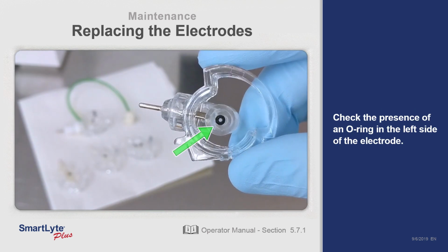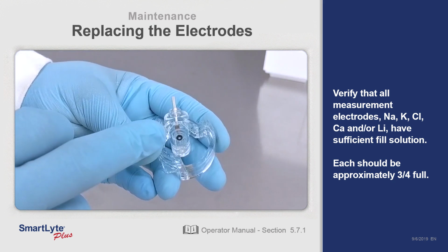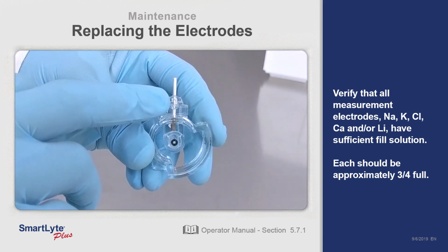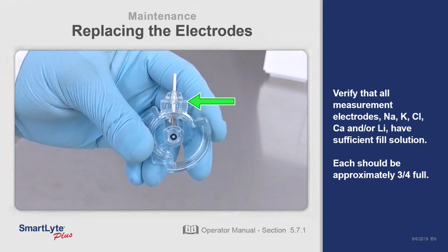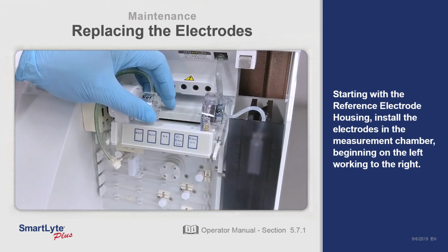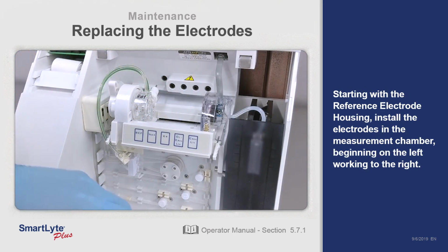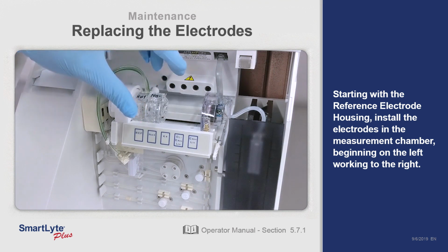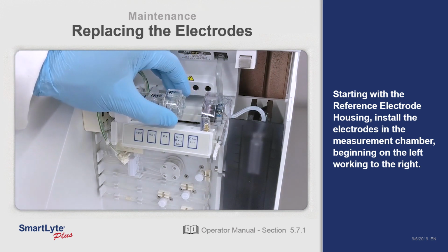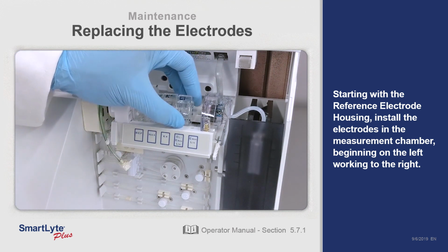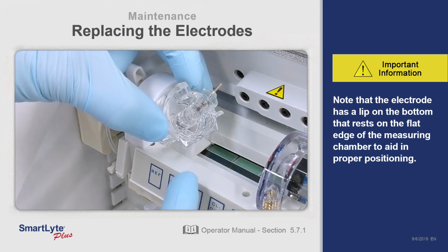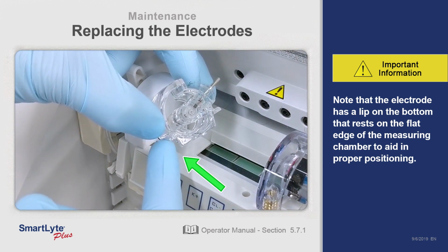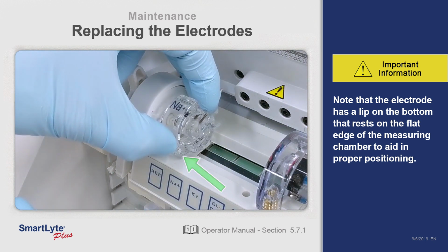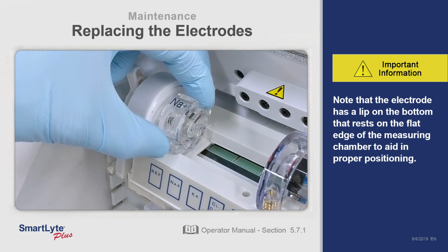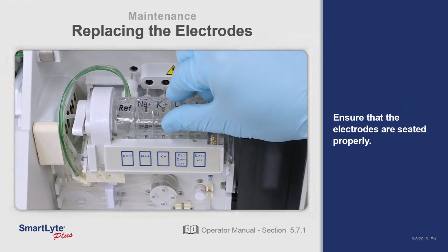Check the presence of an O-ring in the left side of the electrode. Verify that all measurement electrodes have sufficient fill solution. Each should be approximately 3/4 full. Now install the electrodes in the measurement chamber, beginning on the left, working to the right. The reference electrode housing is installed first. Note that the electrode has a lip on the bottom that rests on the flat edge of the measuring chamber to aid in proper positioning. Ensure that the electrodes are seated properly.